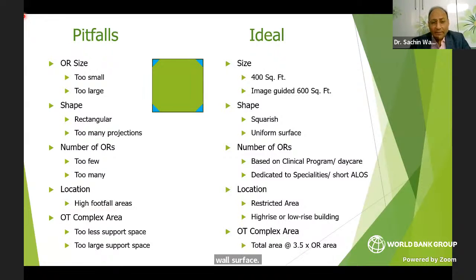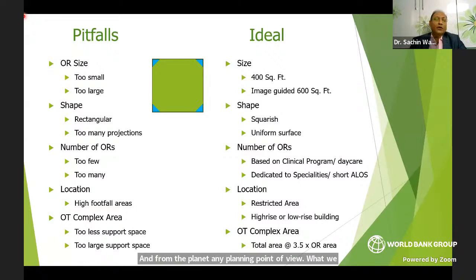And from the planning point of view, what we have seen is that people have either too few OTs or too many OTs. What I mean by too few is that, especially the earlier hospitals, which used to have a thumb rule of, say, 1:50 or 1:60 beds, are facing a crunch of operating rooms. That is because in recent times, the average length of stay of patients after surgery has reduced drastically. Instead of, say, 7 to 8, 10 days, now patients can be discharged on the second or third day itself. The advances in technology have also aided this. And a lot of specialties are doing daycare, like ophthalmology, where you can send the patient home the same day. A lot of daycare surgeries have evolved. So that actually enhances the focus on the operating room number. Your operating room number has to be based on your clinical program and the specialty mix that you have.